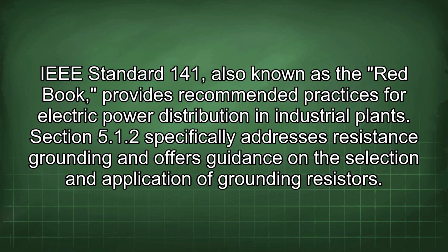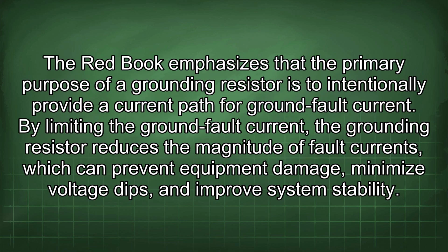of personnel. IEEE Standard 141, also known as the Red Book, provides recommended practices for electric power distribution in industrial plants. Section 5.1.2 specifically addresses resistance grounding and offers guidance on the selection and application of grounding resistors. The Red Book emphasizes that the primary purpose of a grounding resistor is to intentionally provide a current path for ground fault current. By limiting the ground fault current, the grounding resistor reduces the magnitude of fault currents, which can prevent equipment damage, minimize voltage dips, and improve system stability.